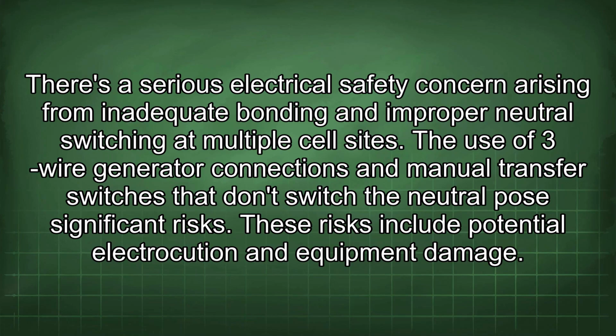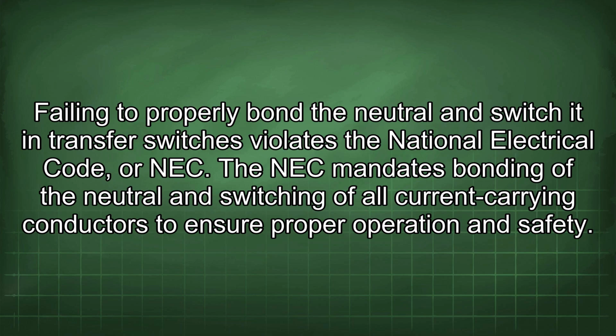There's a serious electrical safety concern arising from inadequate bonding and improper neutral switching at multiple cell sites. The use of 3-wire generator connections and manual transfer switches that don't switch the neutral pose significant risks. These risks include potential electrocution and equipment damage. Failing to properly bond the neutral and switch it in transfer switches violates the National Electrical Code, or NEC. The NEC mandates bonding of the neutral and switching of all current-carrying conductors to ensure proper operation and safety.